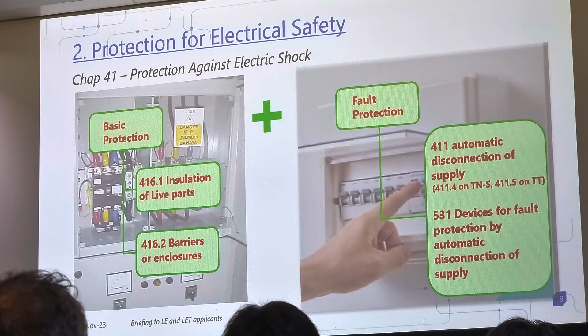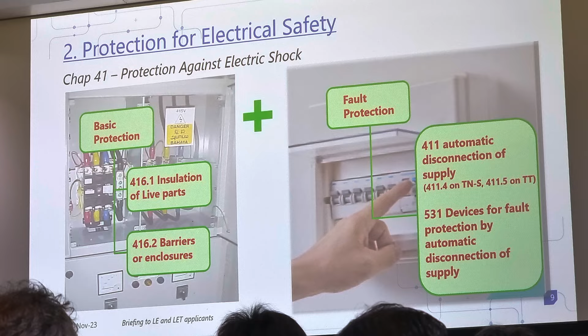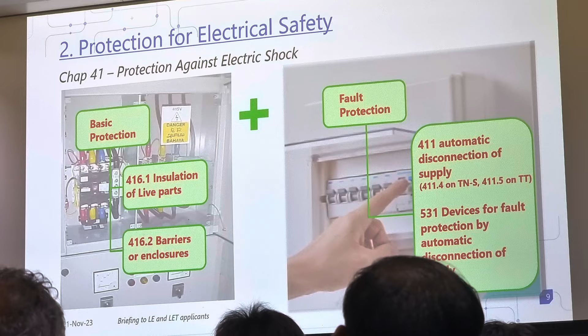PVC sheeting, PVC insulation, cover the conductors so that people can touch them, can handle the conductors, right? So this is protection against live parts. You also have barriers and enclosures. So your DB, your switchboard, they're all fully enclosed so that you will not be able to touch. Okay? That's where the IP2X comes in. What's IP2X? You can find out from 638. Prevent fingers from touching live parts. So these are protection against basic protections.